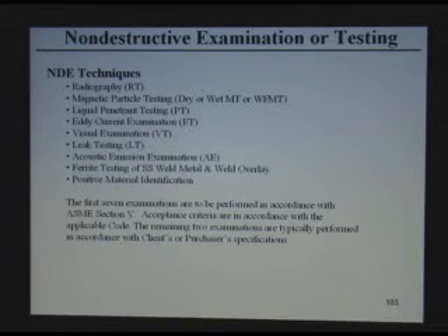Magnetic particle testing detects cracks on the surface and a little bit under the surface. There are different ways. You generate a magnetic field on the surface of the weld or the equipment, and then you spray powder, like iron powder. If there is a crack, it makes a discontinuity in the surface, and you can see a line, which is a crack, so you can say there is a defect. There is dry powder or wet powder, or wet fluorescent magnetic particles, which have fluorescent material in them, like sparks, so you can see them more easily and it is more sensitive.